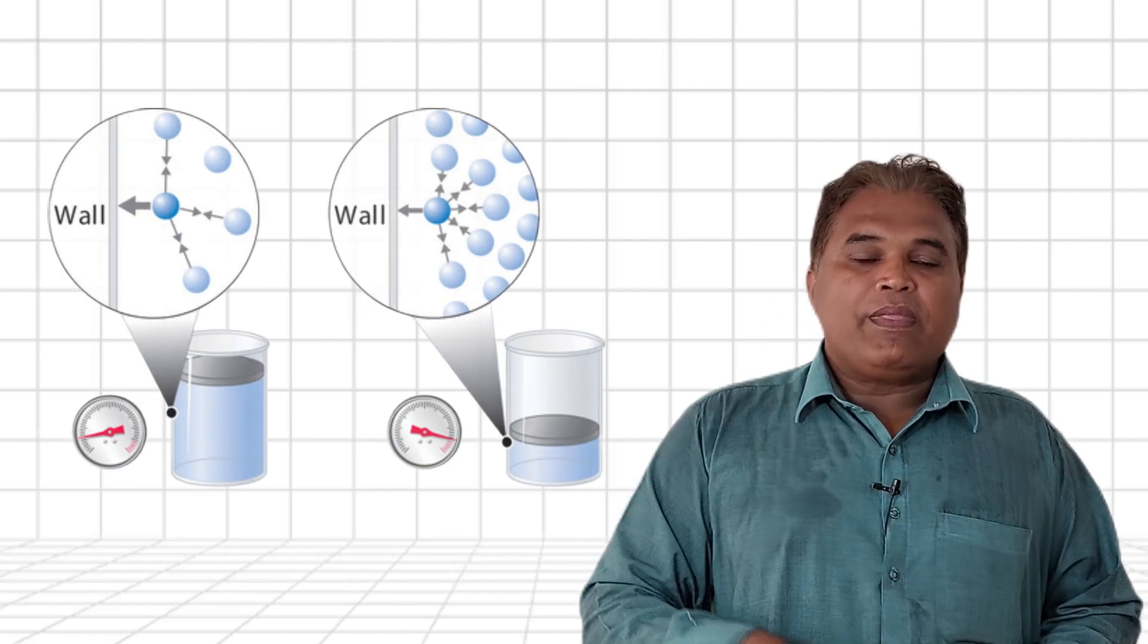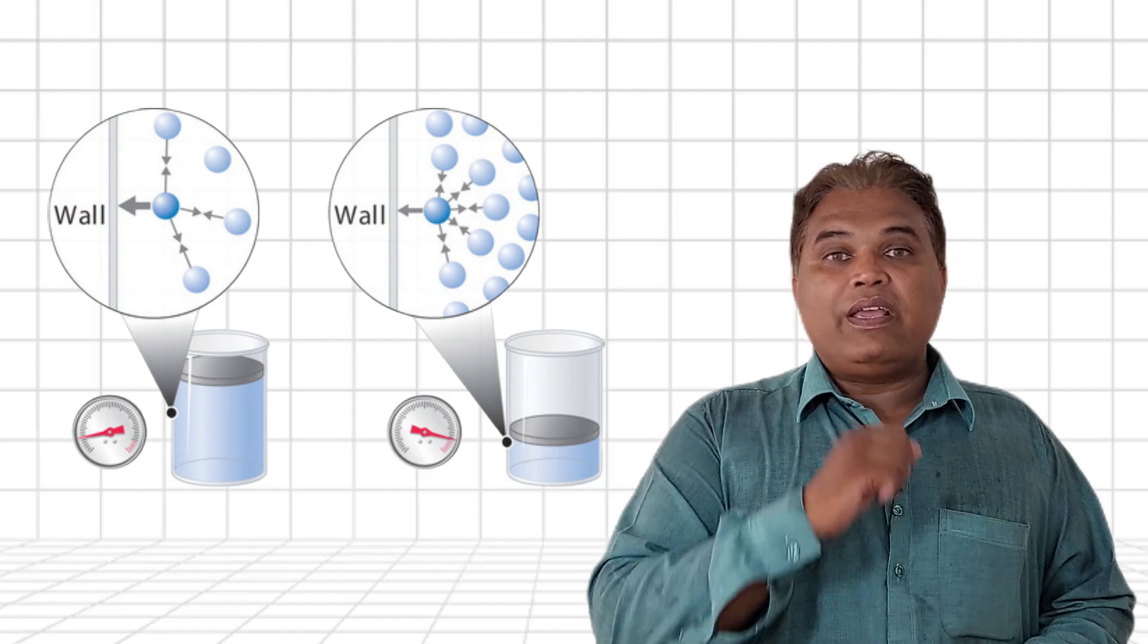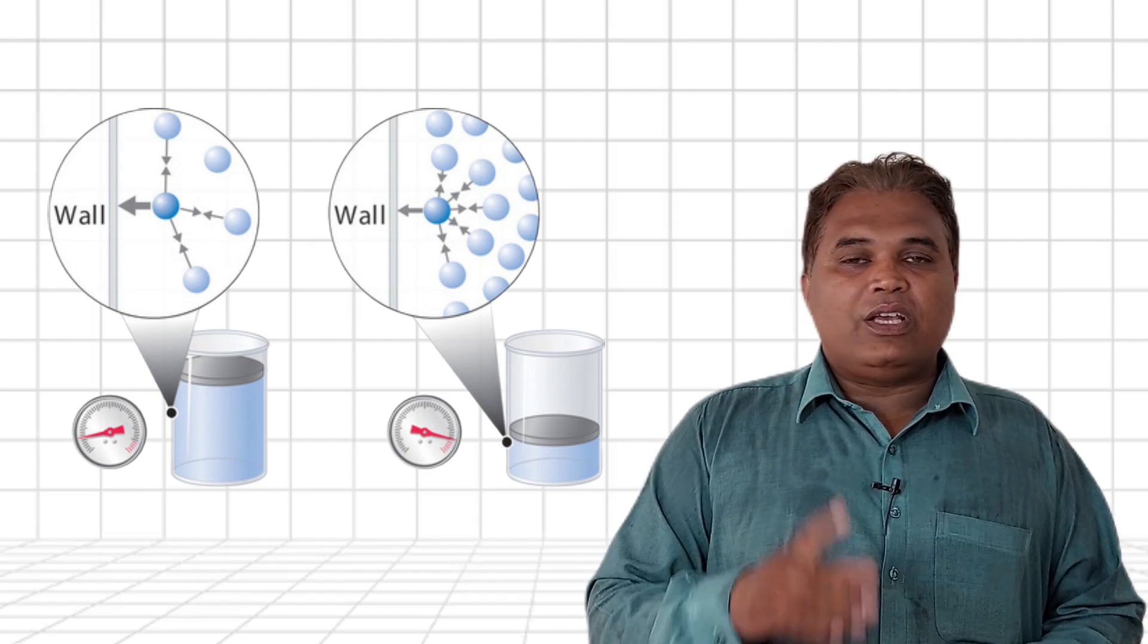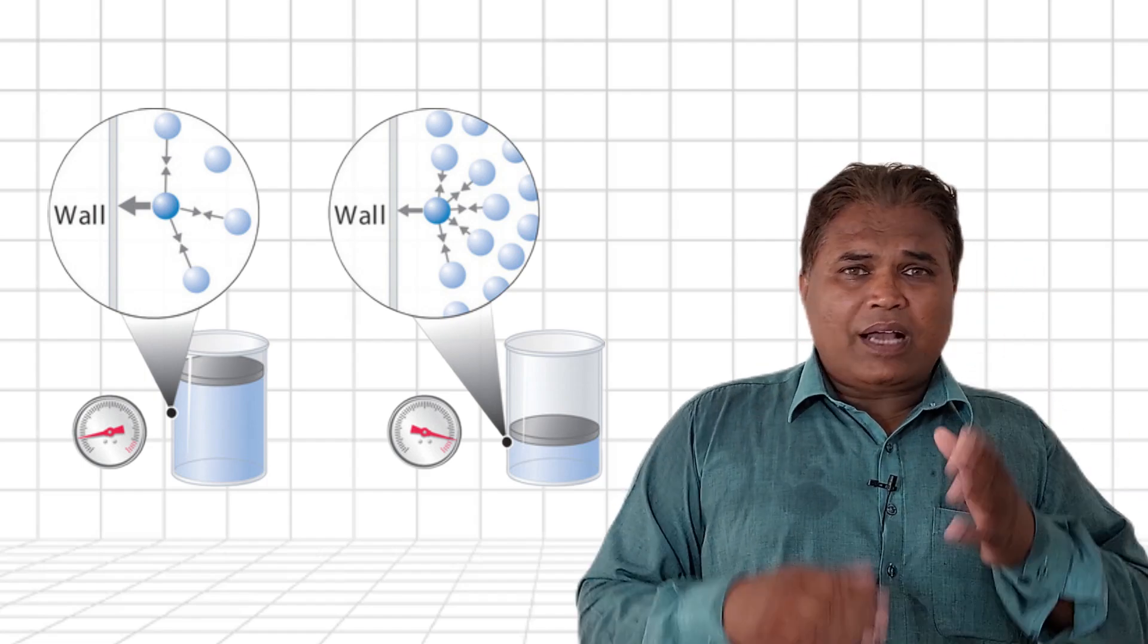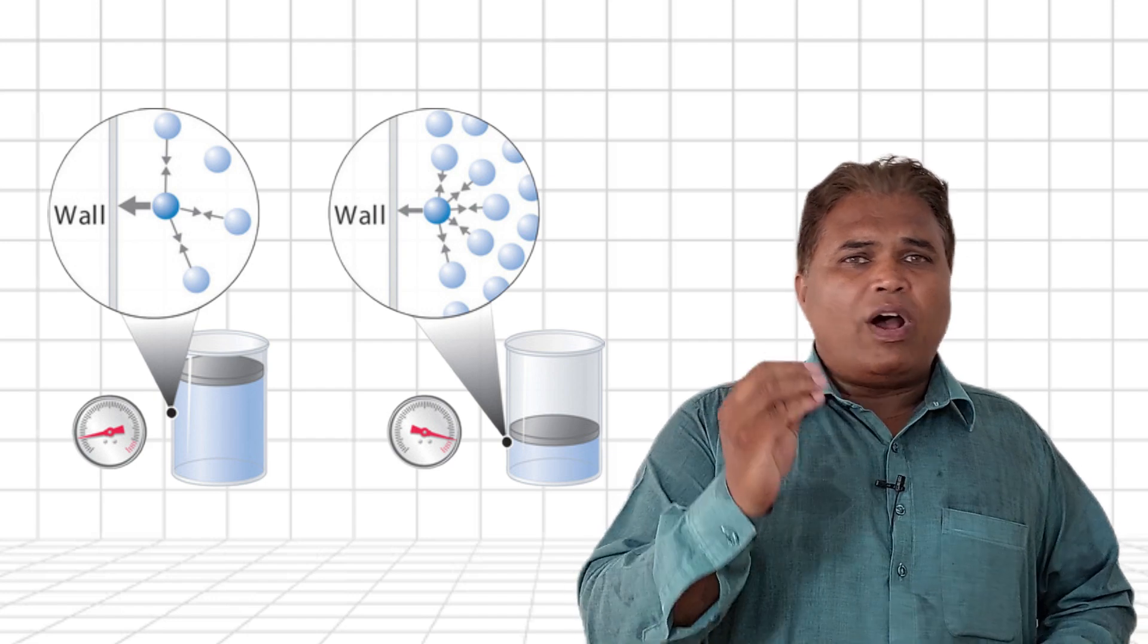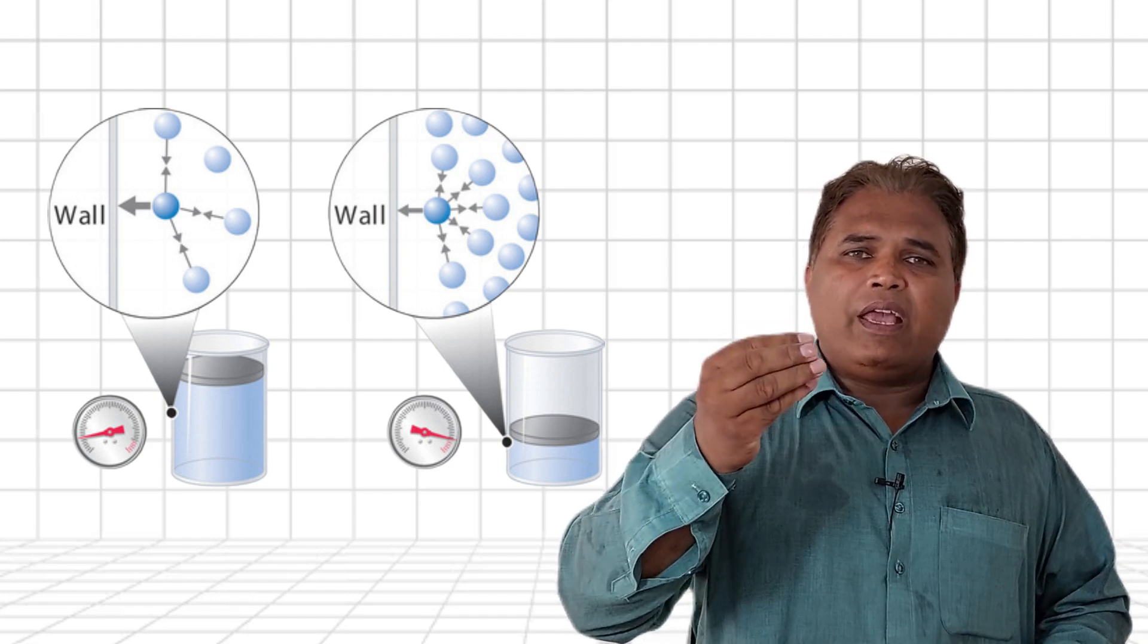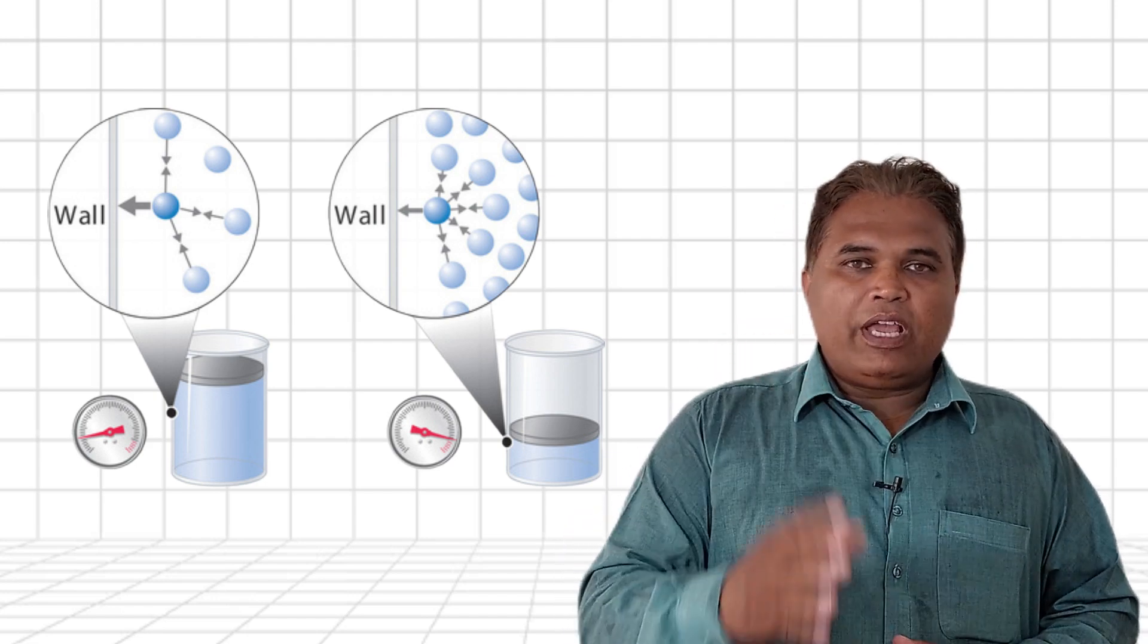This might mislead you into thinking the system requires more gas. When ice forms on the evaporator, the pressure further drops, giving a false impression of insufficient gas.